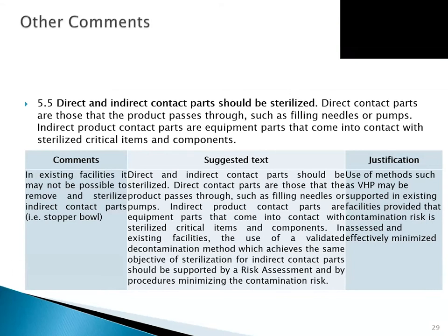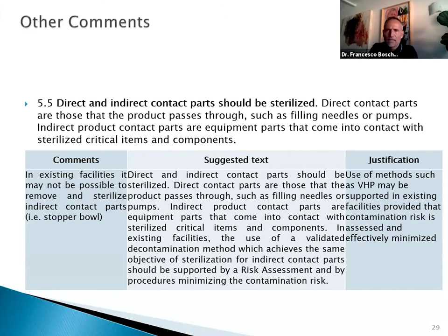For example, with isolators, which are generally very well tooled to protect the product, in some cases in an existing isolator the stopper bowl cannot be dismantled and therefore cannot be sterilized. So we think the use of validated methods such as VHP should be allowed, provided they are supported by a contamination control strategy and effective mitigation.